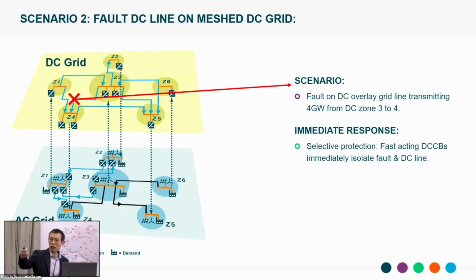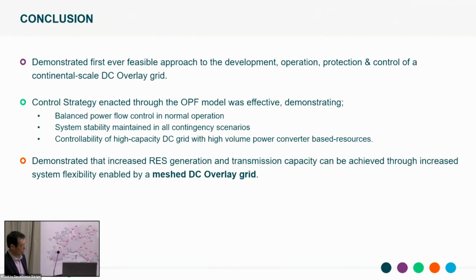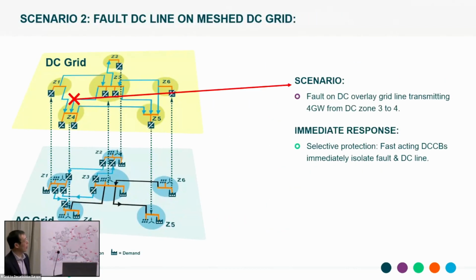I think Dirk mentioned the importance of DC protection. Obviously the detail of DC protection is out of scope of this project. What we consider here is a fully selective DC protection with fast-acting DC circuit breakers installed at the DC line. Once we have a fault, it can be quickly detected, and then we open the DC circuit breaker to quickly isolate the faulty DC line.